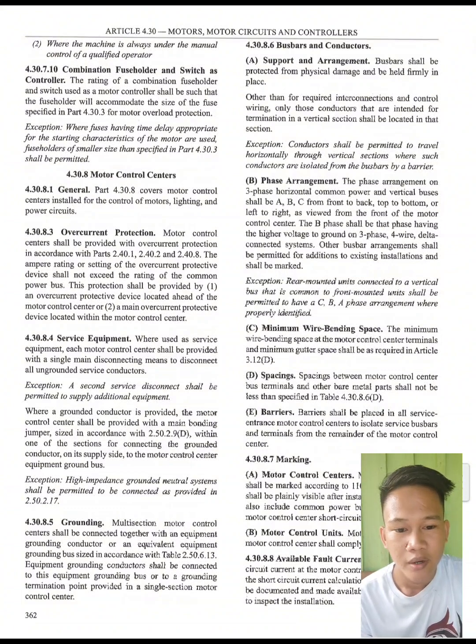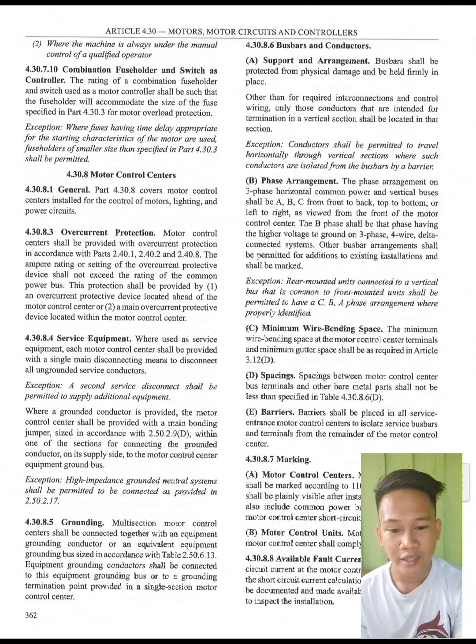Next, we have 4.30.8.4 Service equipment. Where used as service equipment, each motor control center shall be provided with a single main disconnecting means to disconnect all ungrounded service conductors. So, exemption: a second service disconnect shall be permitted to supply additional equipment. Where a grounded conductor is provided, the motor control center shall be provided with a main bonding jumper sized in accordance with 2.50.2.9d within one of the sections for connecting the grounded conductor on its supply side to the motor control center equipment ground bus. So, the exemption: high impedance grounded neutral systems shall be permitted to be connected as provided in 2.50.2.17.